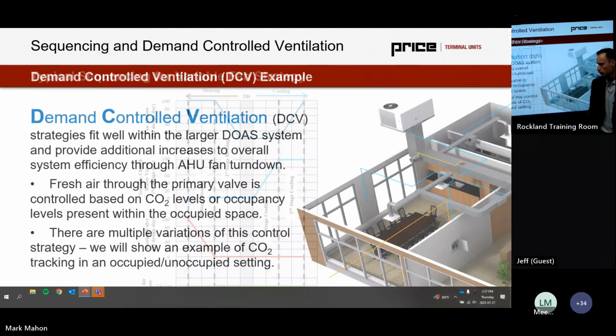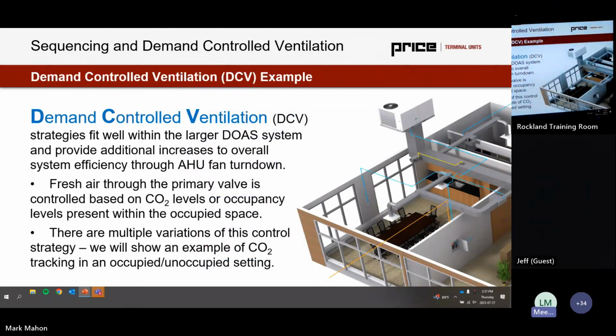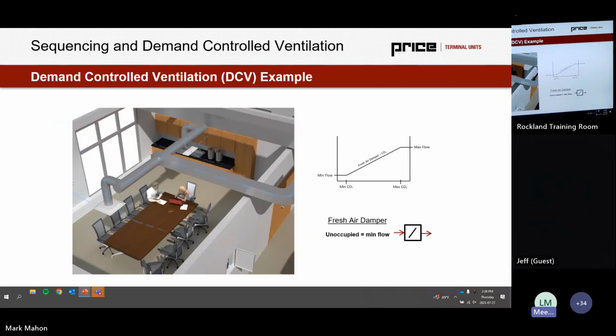This is a decoupled system, so by nature, that means we're going to control the fresh air in a decoupled fashion from the hydronics going through the coil. And the way that this works for us here is generally measuring based off of carbon dioxide levels or occupancy levels within the space as well. So I referred to the Nest Home thermostat. Infrared's a big way. Badge counting is a big way. The most common is measuring and controlling based off of carbon dioxide concentrations.